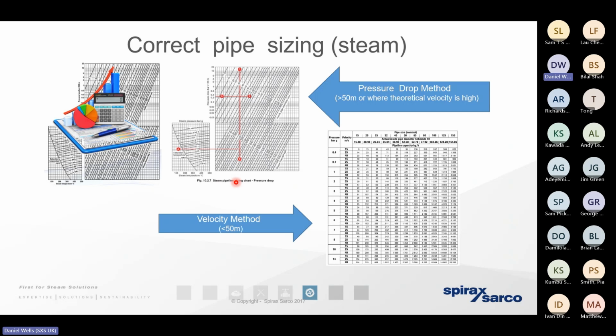Now, if we'd made the mistake of thinking that steam was a gas, or if it was in the perfectly dry condition, as it is referenced by the steam tables, then we may look at moving the steam at perhaps 40 meters per second. That's about 90 miles an hour. So if there was any rust or scale present within the steam, as a result of that erosion or moisture being present, moving that at 90 miles an hour is very quickly going to create more and more problems of erosion of sensitive items of capital equipment like control valves, pressure reducing valves or even flow meters. So if we suspected that the steam was in a poor condition, we'd want to move the steam at a much more gradual velocity, 15 meters per second, for example.